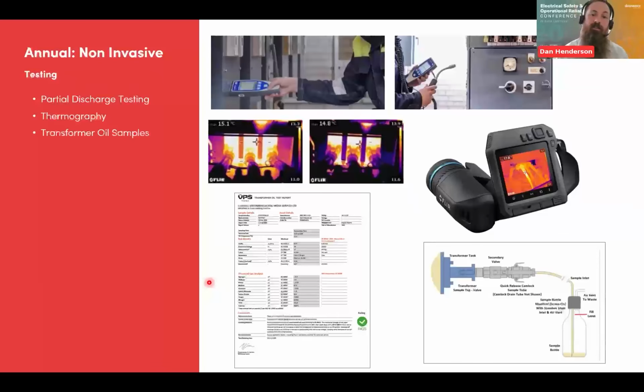Non-invasive testing continued. We're going to cover this more in depth than other ones because we're going to have some SMEs actually talking through what it is, how it comes about, how to detect it, how to interpret it. So I'll just touch on it now, but partial discharge is a massive tool in our wheelhouse, what we can use to identify low-lying faults before they actually escalate into an overarching failure. If there's a gap in a joint or a void or a bad connection, we'll start picking that up in low levels of corona discharge really early on if we're doing our regular inspections. Whereas as it starts getting bigger and bigger, we're leading more towards an actual failure.